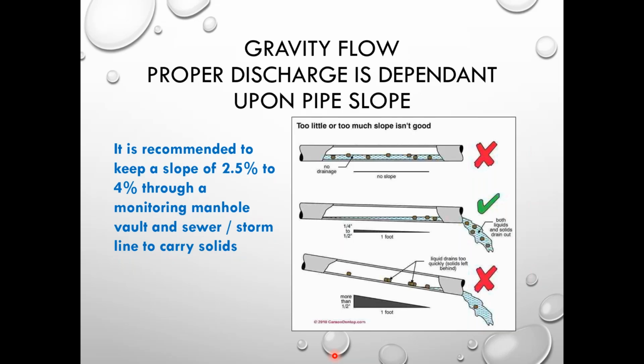This just kind of gives you an idea of gravity flow. Believe it or not, I've shown up at many different industrial facilities, and they have the first area, which is no slope. And so the liquid's backed up, you've got low velocities, and a lot of times they'll have debris and silt and very little drainage on a line. This can wreak havoc on your open channel flow meters. You typically want to have at least a 2.5% to 4% fall through the manhole and line so that it'll take solids with the liquids.